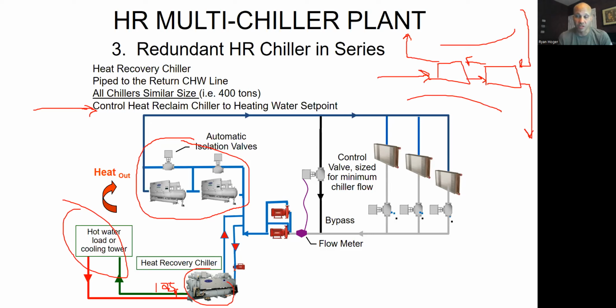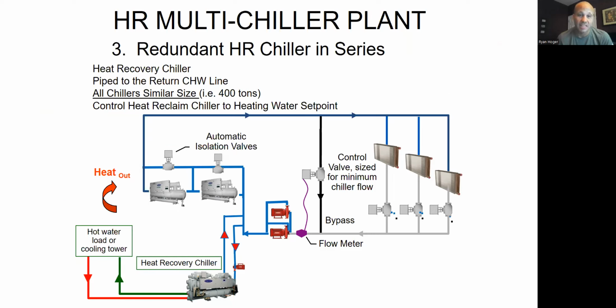And this is a pretty efficient way to run 2 chillers in series. In fact, if you're putting any chillers in series, you should probably put them in series counterflow. Stop putting them in just straight up series. It's not a very efficient way to do it compared to series counterflow. You can typically get an extra 10 to 15% efficiency for series counterflow over straight series. So whenever we have chiller plants that we already have in series counterflow, or we want to design them into series counterflow on purpose, we'll pretty much set it up this way.